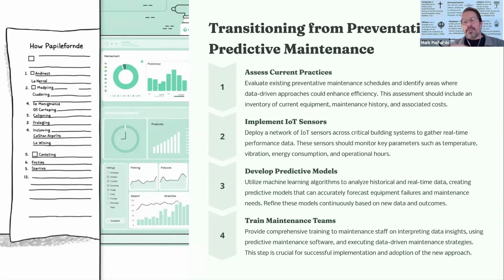So as you develop your predictive models, you're using learning algorithms to analyze historical and real-time data to make real-time decisions. The beauty of this is that with the control systems, a lot of those decisions are going to be made for the real-time aspect of it. The control system is going to say, I have this much humidity, I've got to make this change to the system to combat that, to keep within this range. The temperature is this, the vibration is this, and it can start making modifications to itself, but it also can give you that, hey, I have a problem and I need your help.